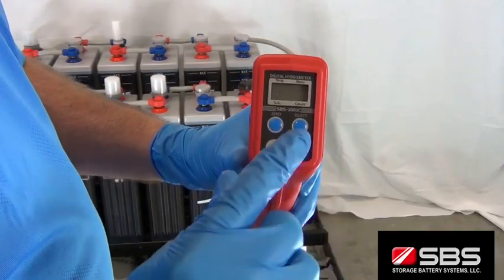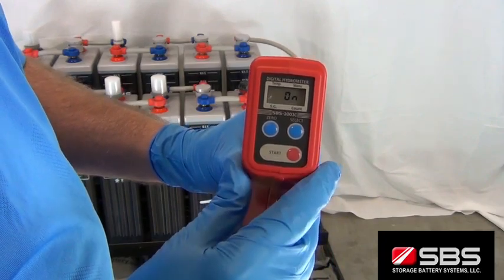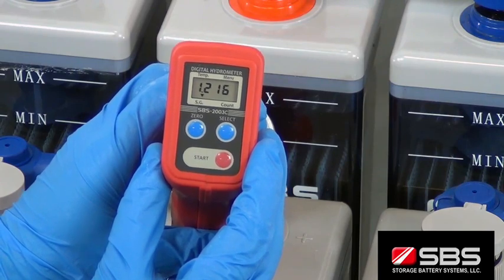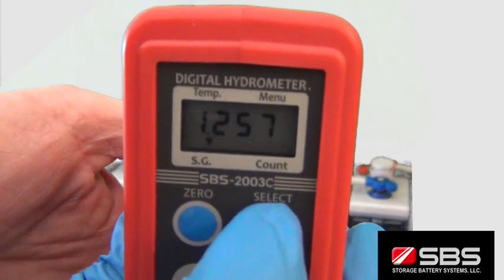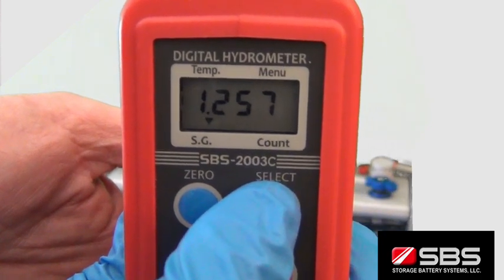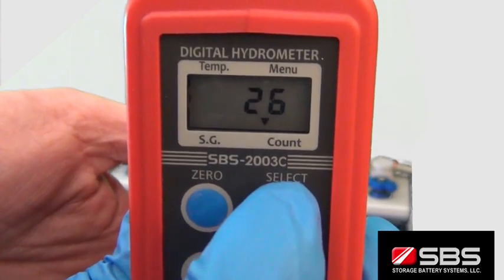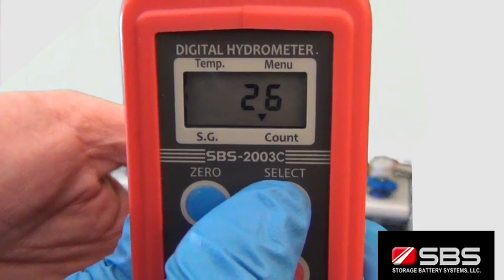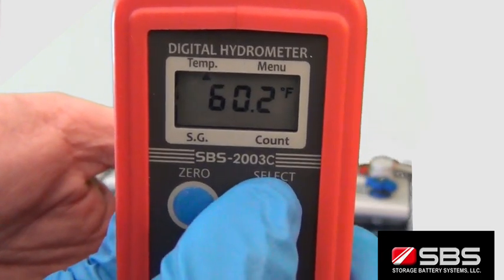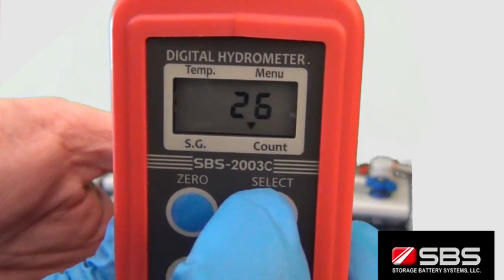Press the red start button to begin the measurement, and within three seconds, a temperature corrected specific gravity reading is displayed. If you wish to also view the sample's temperature or sample count, press the select button to toggle between readings. At this point, the SBS 2003 has recorded the readings in its internal memory and advanced the count by one, and you're ready to take your next reading.